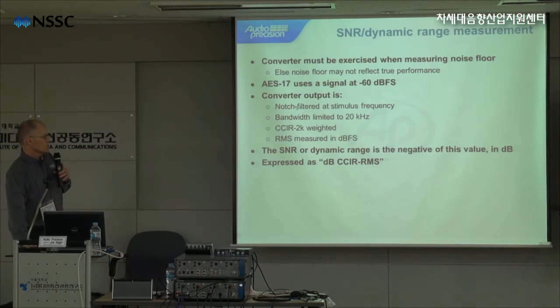So this notch filters out this low-level signal at minus 60 dBFS, and the bandwidth is limited to 20K. It uses the CCIR 2K weighting filter, and the RMS level is then measured in dBFS. The signal-to-noise ratio or dynamic range is the negative of this value in dB, and it's expressed as dB CCIR-RMS.